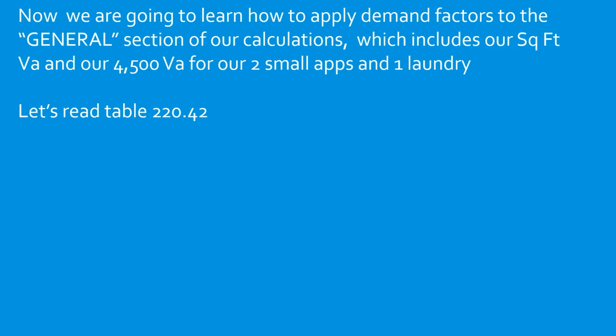All right, so when we find ourselves in table 220.42, the first thing we're going to do is stop and read the black bold heading to make sure we're in the right table. It says lighting load demand factors. Boom, I feel like we're in the right table. And then remember, we always read our tables from top to bottom and left to right using the black bold headings to navigate. So let's start at the left-hand side. The first black bold heading we come to says type of occupancy. And if you look down through there, it's pretty self-explanatory. If that type of occupancy is listed in there, then you're allowed to use these demand factors.